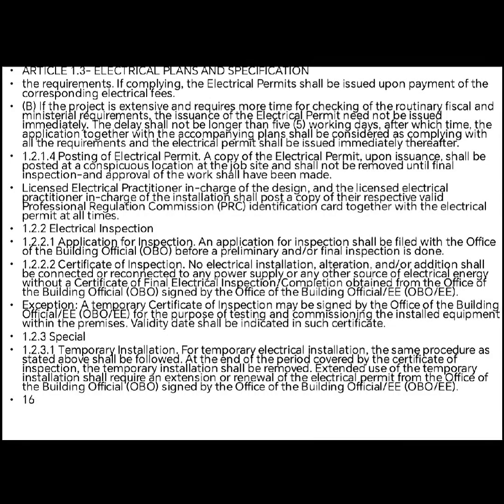3. Inspection requirements. The work must be done by a licensed electrical practitioner who signs the design. And applications for inspections must be filed with the Office of the Building Official (OBO), just called OBO, for preliminary and/or final inspections. Number 4, electrical inspections. No electrical installation can be energized until it passes inspection and gets a certificate of inspection from the OBO. A temporary certificate may be issued for testing equipment within the premises with a specified validity date.